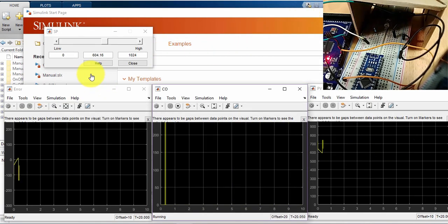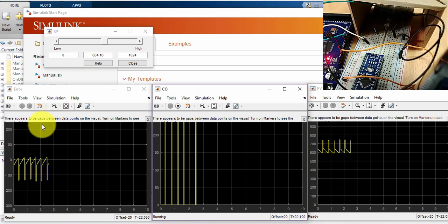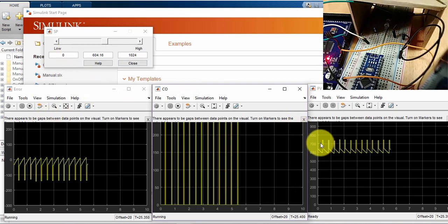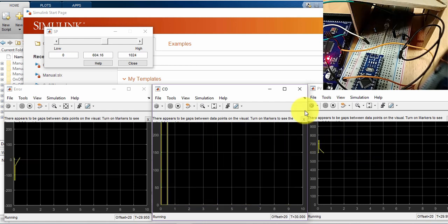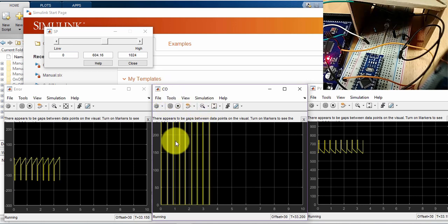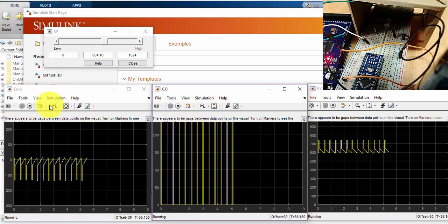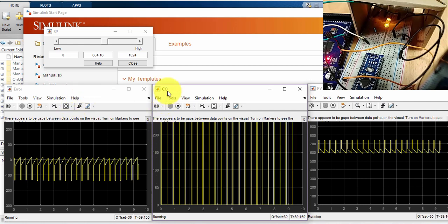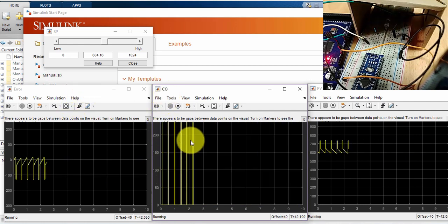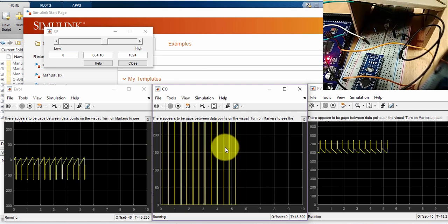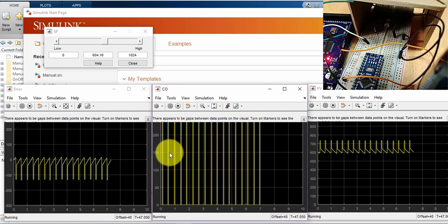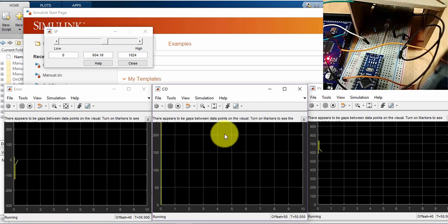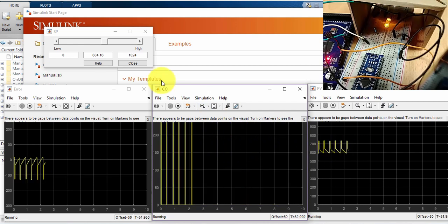So what happens here, my set point is 600, I can see 604, the PV is hovering around. This is the PV scope, this is the controller output scope, and this is the error scope. Just a reminder, in manual control, I used to change this by the slider gain, now the controller is turning the output on and off, that's why it is on and off.